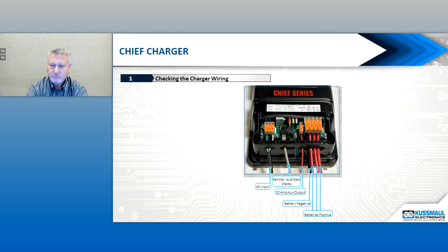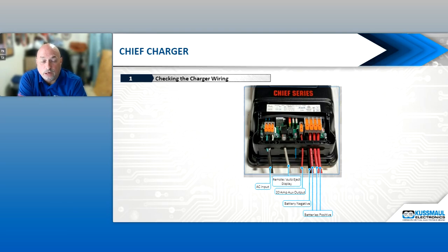One rule of thumb we use to pick the correct charger for your truck is to estimate 5 amps per battery. So if you have 6 batteries on the truck, that's already 30 amps, meaning you need at least a 30 amp charger just to charge the batteries. That leaves you about 10 amps for parasitic loads if those loads are on all the time. That's also why, as you'll see in the upcoming slides, we made the Chief a 40 amp charger, and we also offer a 60 amp, because we never take anything off a truck, we're always adding to it. So it's important to pick the right charger and test the parasitic load. The way to do that is to have all those loads on and running at the same time, put your clamp meter around the positive cable on your battery, and it will show you what current is flowing out of the batteries, that's your parasitic load. Then you can size your charger accordingly.